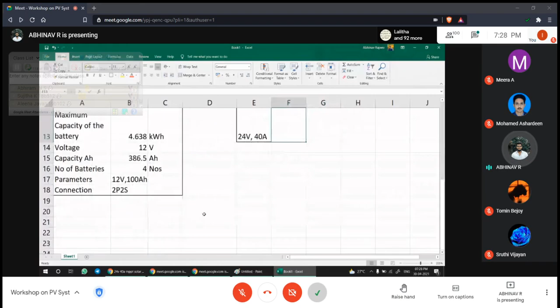Now what? Solar panels. The other derating factors are there. If you need, you can use that. For a lead acid battery, we'll only be getting a depth of discharge up to a maximum of 60%. So we have to multiply again with that. There are multiple derating factors. We are going for a simple basic calculation only here.